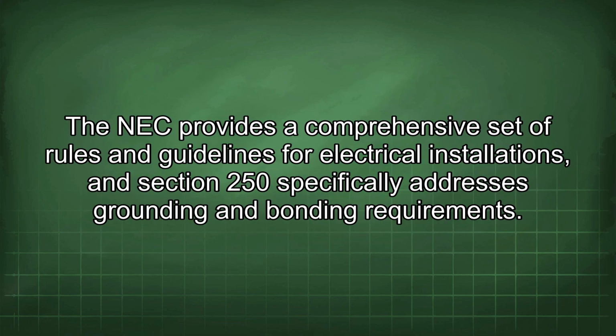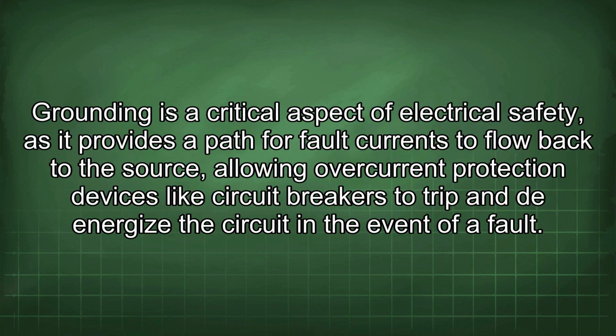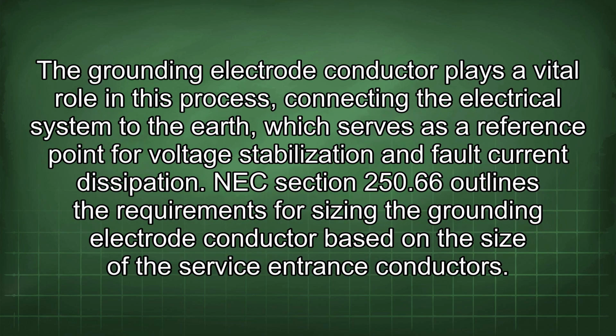The NEC provides a comprehensive set of rules and guidelines for electrical installations, and Section 250 specifically addresses grounding and bonding requirements. Grounding is a critical aspect of electrical safety, as it provides a path for fault currents to flow back to the source, allowing overcurrent protection devices like circuit breakers to trip and de-energize the circuit in the event of a fault. The grounding electrode conductor plays a vital role in this process, connecting the electrical system to the earth, which serves as a reference point for voltage stabilization and fault current dissipation.